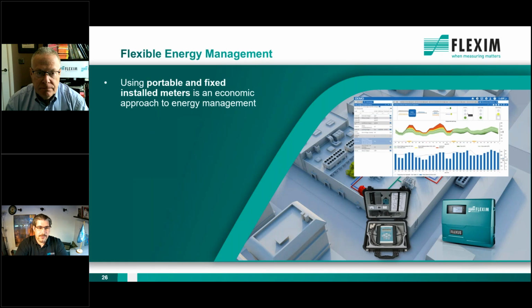Another thing, very interesting for practical use, is what I already told you about the portable meter: it's basically the same principle and can do the same as the fixed installed one. So having a combination of portable and fixed installed meters is a very economic approach to your energy management and to the road to carbon net zero. Because if you want to have a perfect picture, you would need a lot of installed meters. You need to purchase them, install them, and hook them up to your system. But there's also the possibility of having just the needed amount of fixed installed meters, and everything else can be covered by portable meters. So this is absolutely okay.